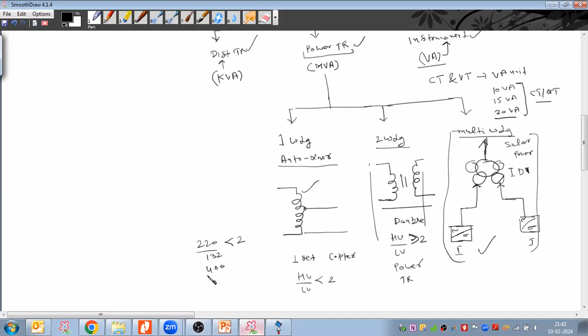This is whenever my HV voltage to LV voltage ratio is less than 2. For example, in my case, 220 by 132 kV, so this ratio is less than 2. Another example, 400 kV divided by 220 kV is also less than 2. Let us be precise and divide this: 400 kV divided by 220 kV gives a ratio of 1.8, which is less than 2. In that case, as a design engineer, we select the auto transformer, or single winding transformer.